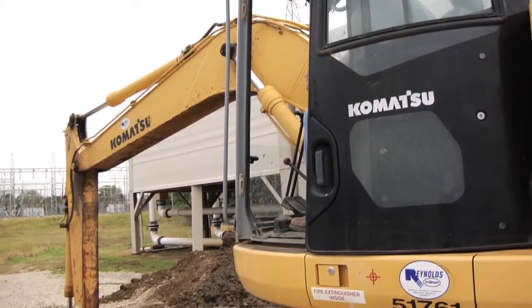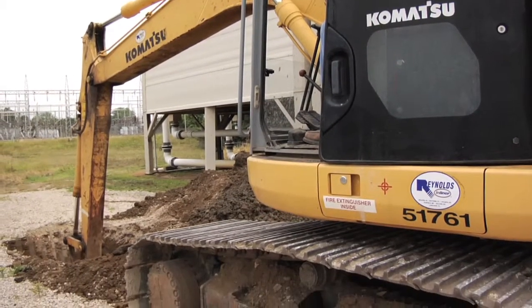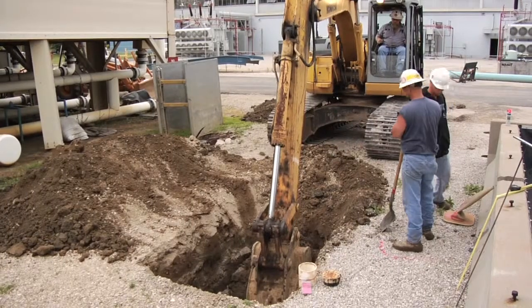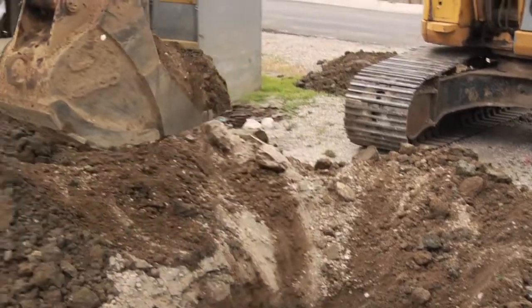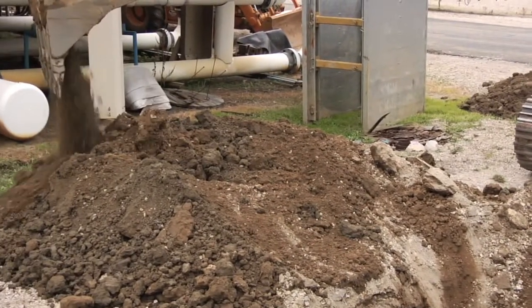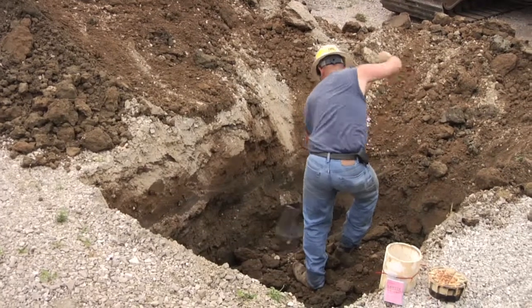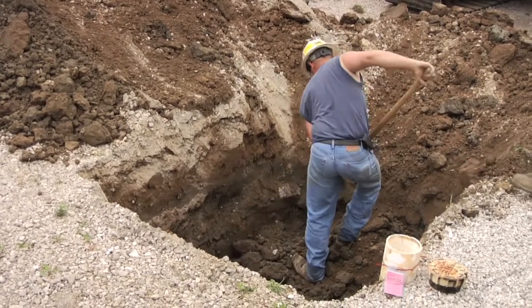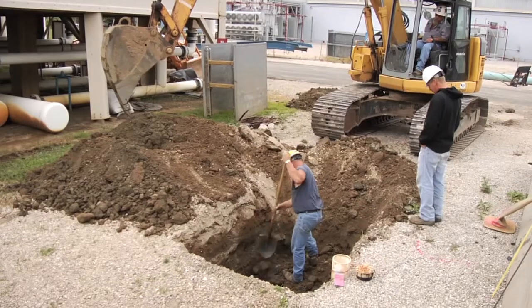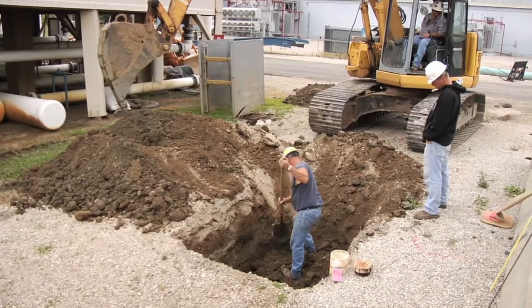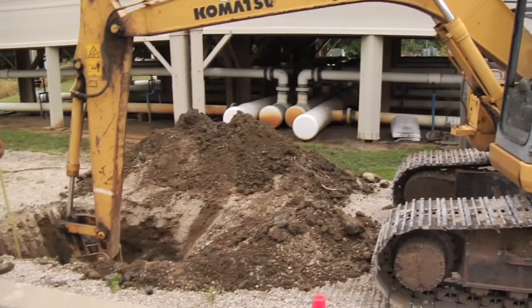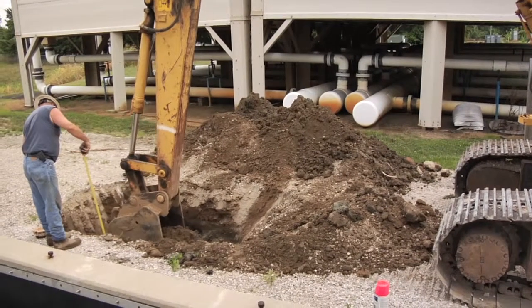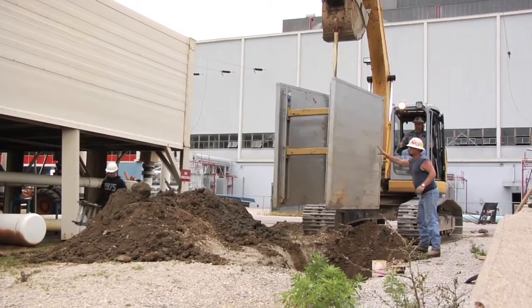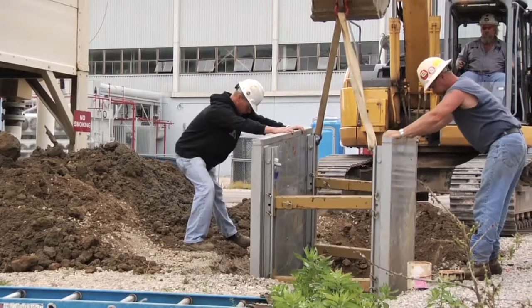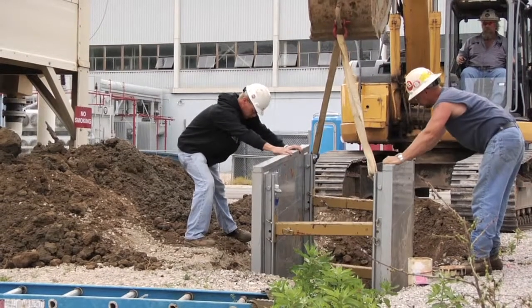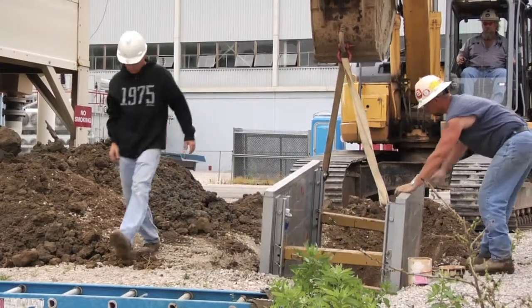Most soil at Hoosier Energy facilities is considered Type C or previously disturbed. Before any digging or excavating is done, an excavations and trenching work permit must be completed. The site must be marked with flashing warning lights or orange barricade fencing at the end of each day or when work is not being performed for an extended time. Remember, OSHA requires that if you're excavating 4 feet or deeper, the space may be considered a confined space. Appropriate protection from cave-ins will be required. These methods may be sloping, shoring, or using a trench box.